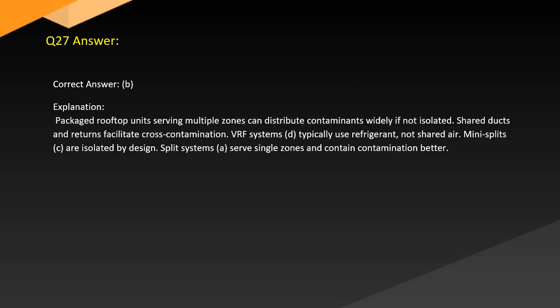Answer. Correct answer: B. Explanation. Packaged rooftop units serving multiple zones can distribute contaminants widely if not isolated. Shared ducts and returns facilitate cross-contamination. VRF systems (D) typically use refrigerant, not shared air. Mini splits (C) are isolated by design. Split systems (A) serve single zones and contain contamination better.